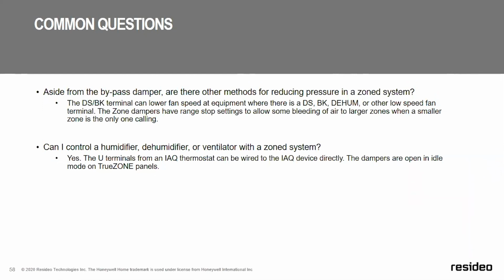What I'm going to do is call for my highest stage of cooling. I do it in cooling mode because that's when I'm going to get the most airflow through my system. So I call for my highest stage of cooling, look at the bypass damper indicator, and make sure that it is closed. Note, I'm calling for my highest stage of cooling with all of my dampers open, so all of my zones are calling. The reason I'm doing this is I'm trying to eliminate the zone system from the equation. With all my dampers open, I've essentially eliminated my zoning, and I want to make sure that I'm not bypassing any air in that situation.